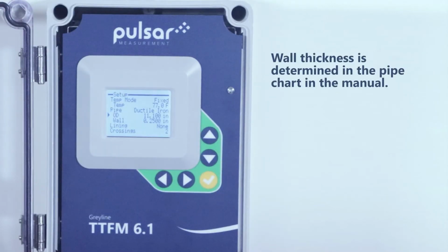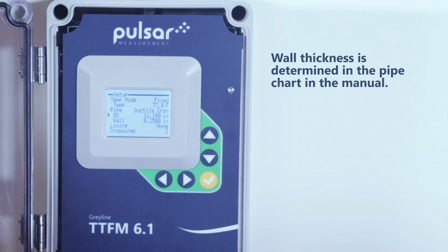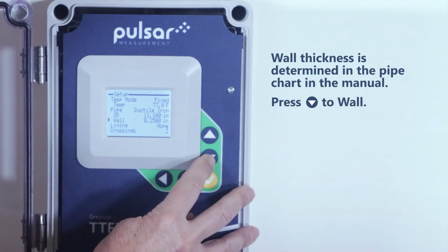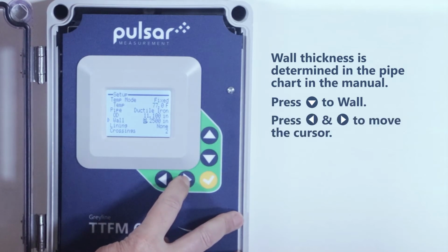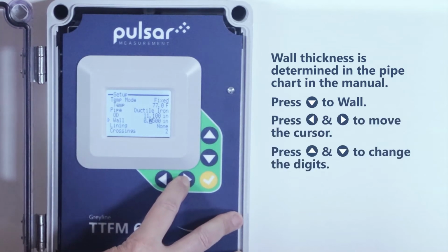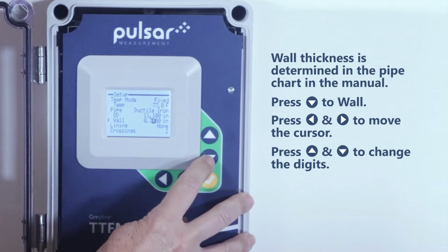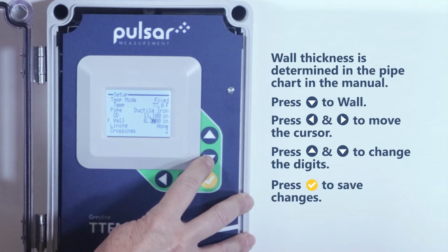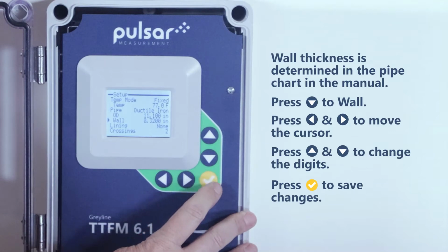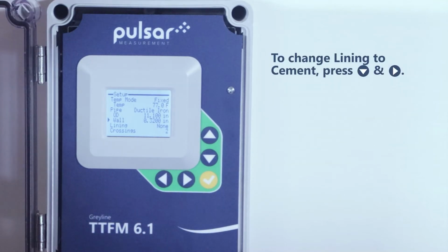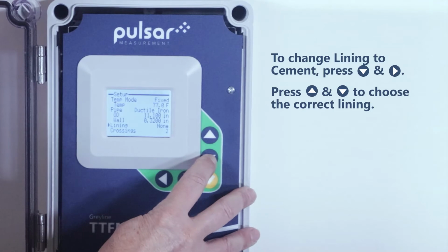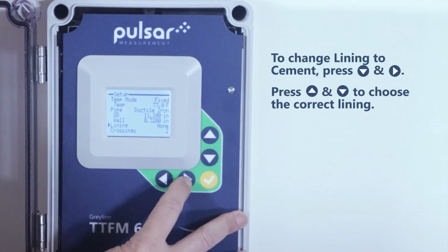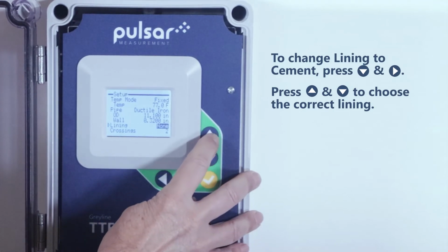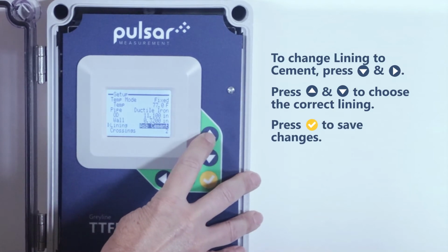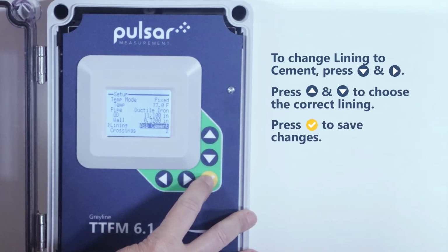From the same pipe chart, the wall thickness should be set to 0.32 inches. We'll do this by hitting the down arrow button, then the right arrow button, and making the change. Remember, hit the check mark to make the change permanent. Our lining should be changed to cement. We'll hit the down arrow button, followed by the right arrow button until we find cement. Remember, check mark to make the change permanent.